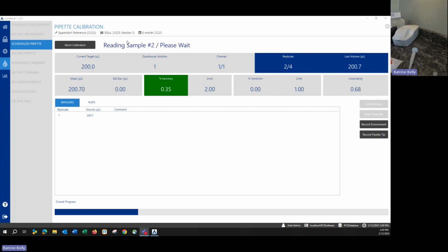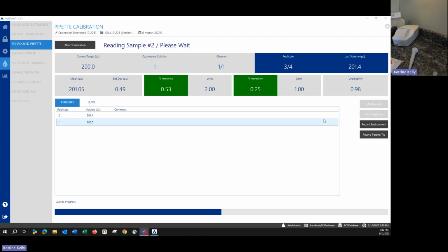Now, I do want to call your attention to the right-hand side of the screen over here. There's two buttons that are grayed out. They're not available to me right now. For my next data point, I am going to over-deliver. So I'm going to depress the plunger down to the second stop to aspirate. And then I'm going to intentionally over-deliver so you can see what happens when there's a failure.